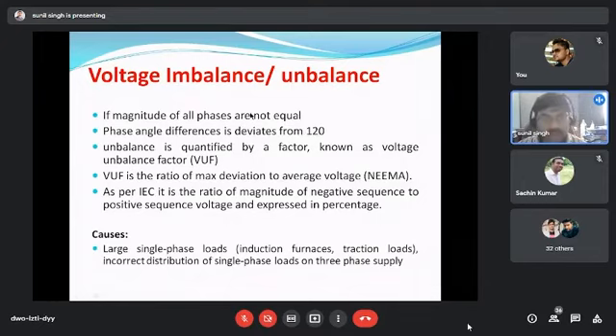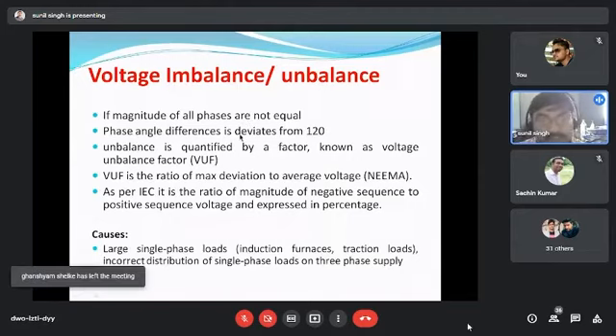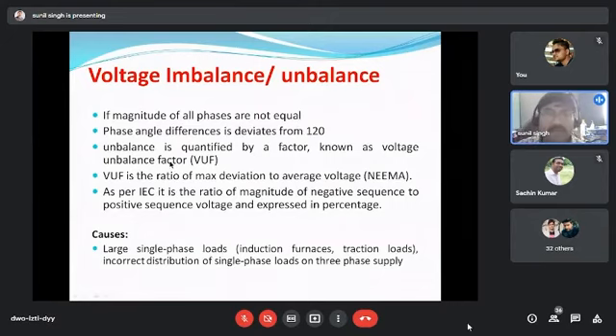If the magnitudes are not equal, it is voltage unbalance. If the magnitudes are equal and the phase angles are not 120 degrees, again it is a voltage unbalance problem. A mixture of these two is a hybrid type of voltage unbalance problem. Voltage unbalance is generally quantified by a factor known as the voltage unbalance factor, VUF. As per the NEMA standard, VUF is the ratio of the maximum deviation to the average. Maximum deviation to the average.